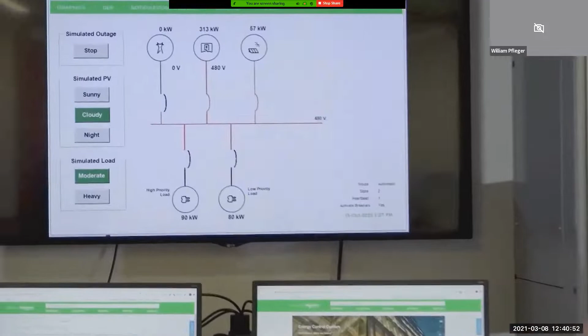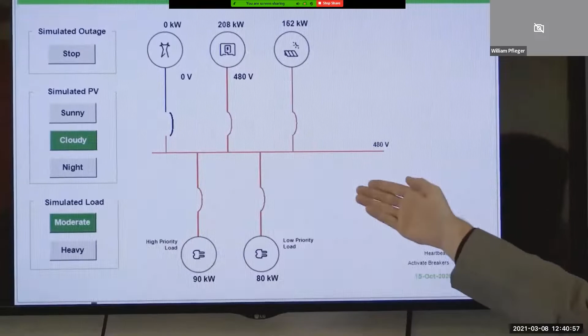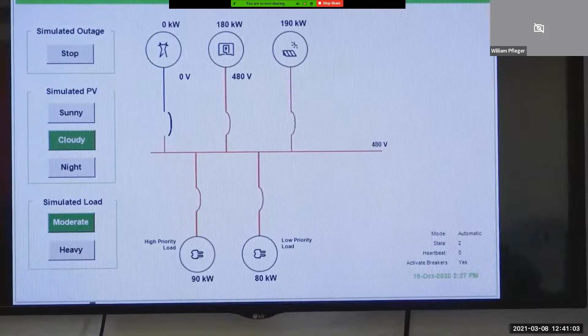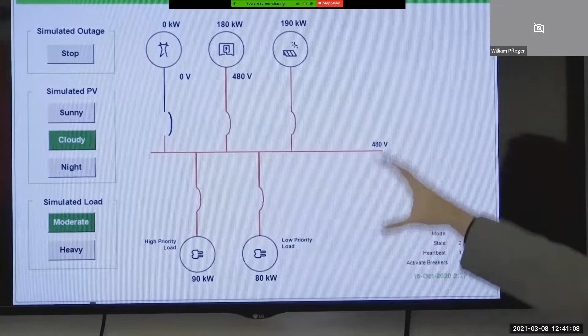So you see the utility voltage went to 0. The generator's fired up to 480. 1, 2, 3, breakers click in. That's the generator breaker closing after we gave the generator a few seconds to warm up and stabilize. And then we sequence in the high priority and low priority loads. And so now you see, here we are islanding and everything is back on despite the utility being down.